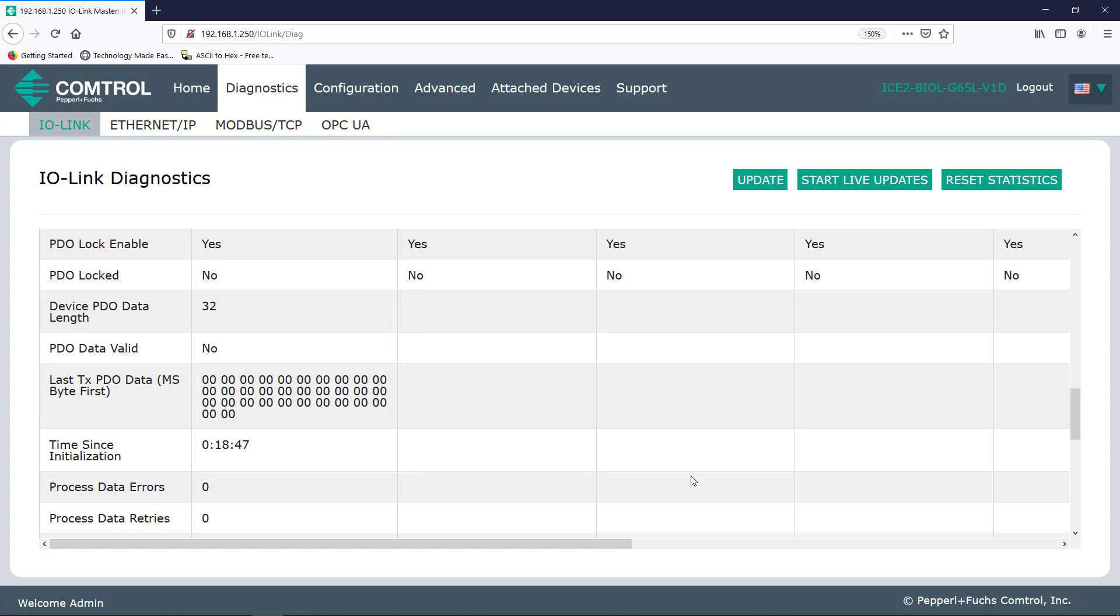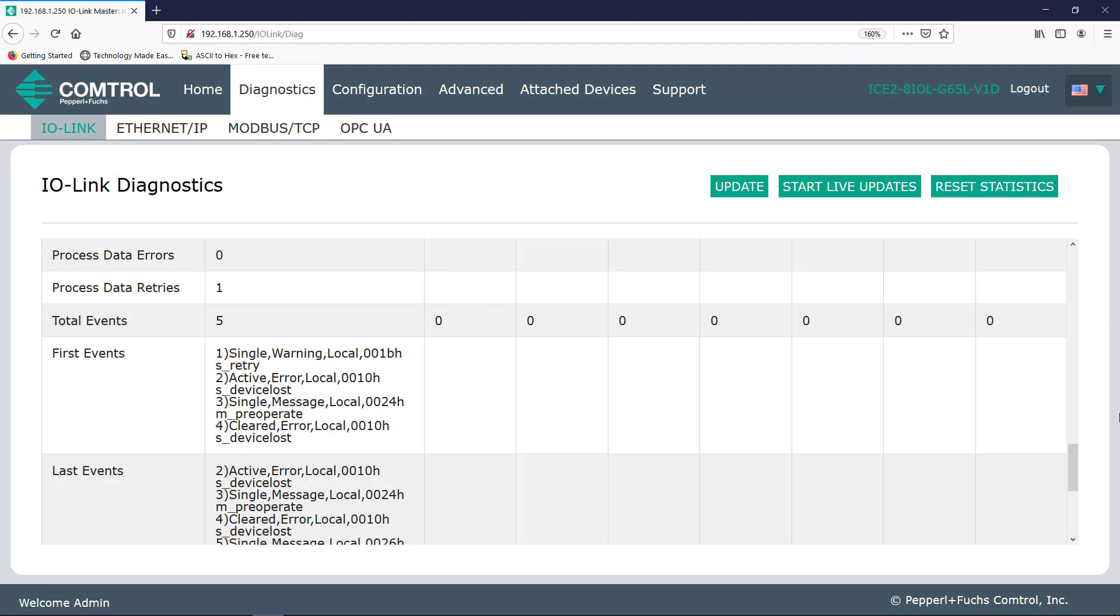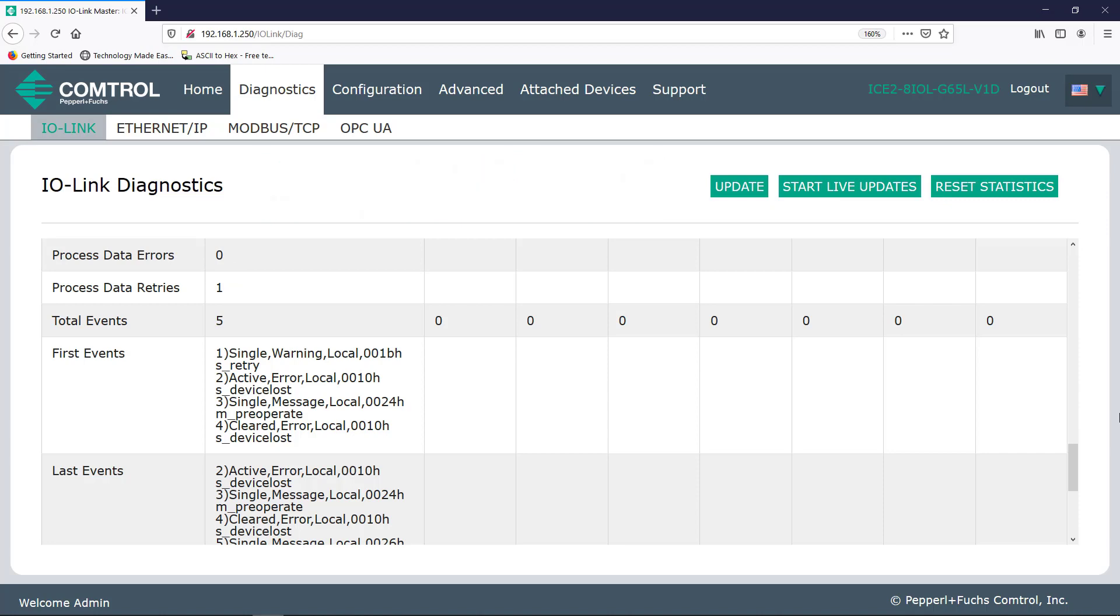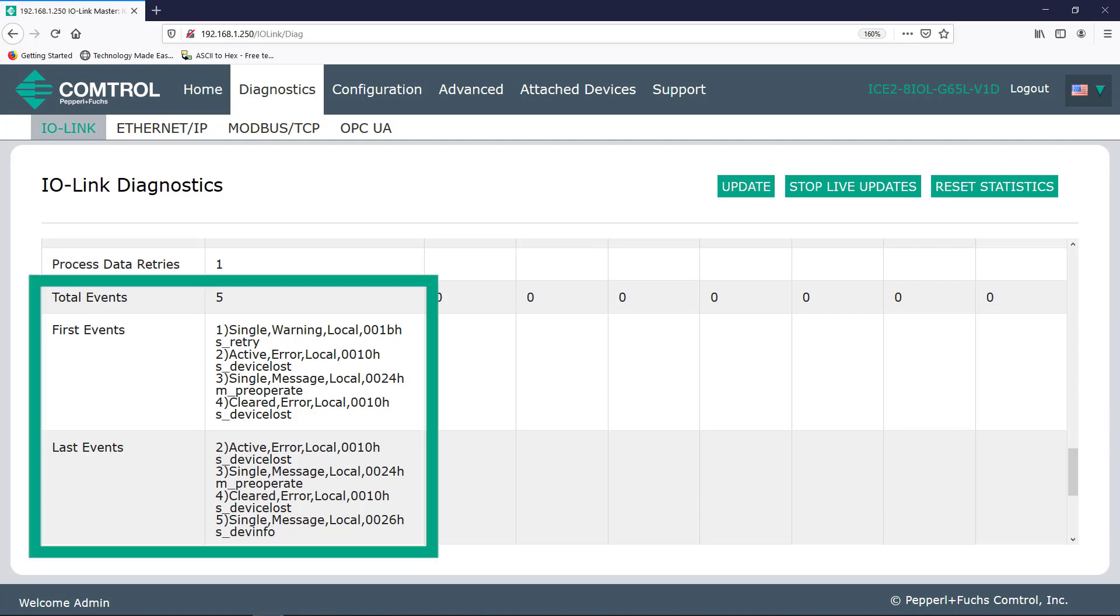And next we see time since initialization. So if I remove and then plug my RFID head back in or repower up my ICE2 IO-Link master, the time since initialization will go back to zero. Now, so far I've got no process data errors, but since I just removed the IO-Link device while the master was trying to communicate, I can now see a number showing in the process data retries. Underneath that, I can even see the total number of events with descriptions, which occurred mostly due to my actions.